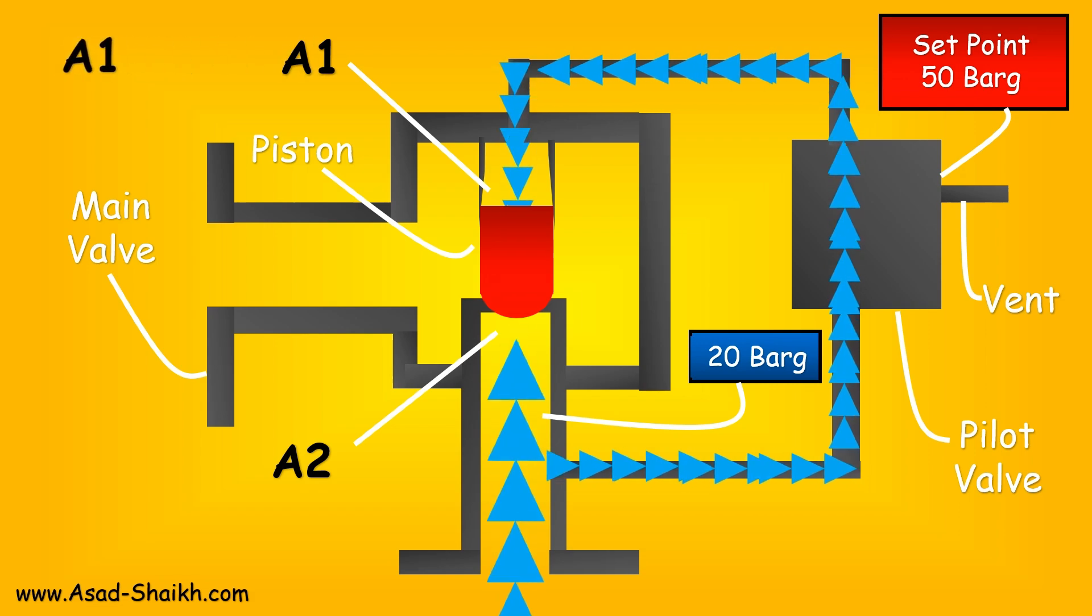This inlet pressure of 20 bar is also reaching from the pilot to the other side of the piston, and the area A1 is greater than the area A2. This is very important to note, and this is how all relief valves, especially pilot relief valves, are made.